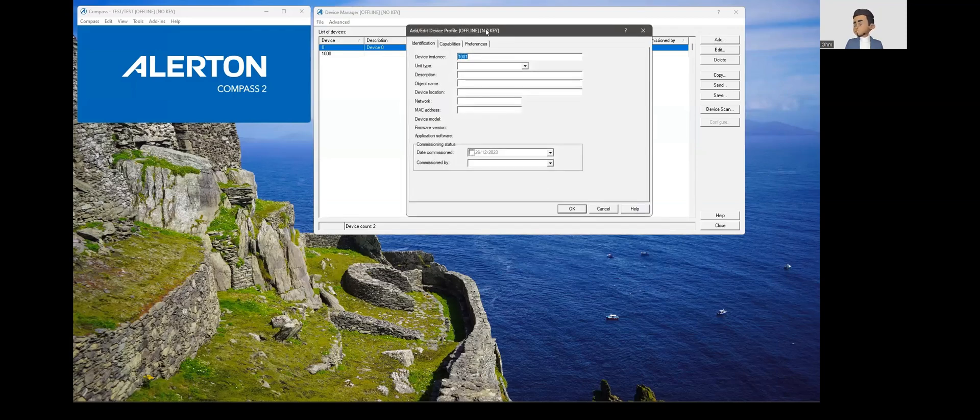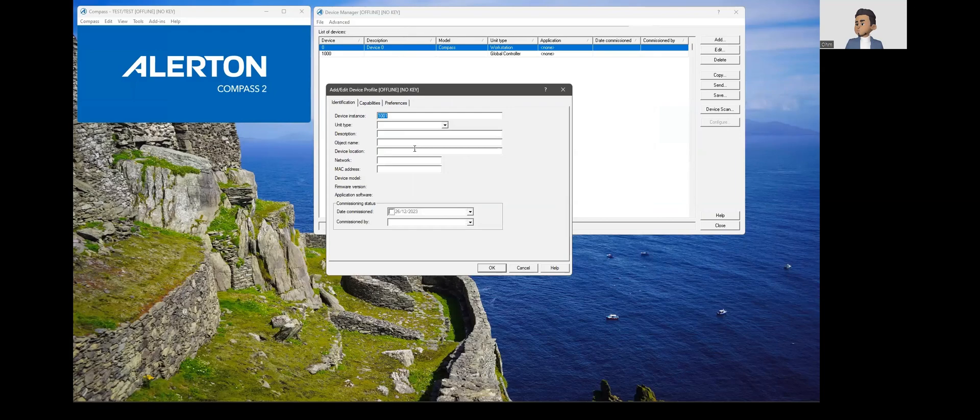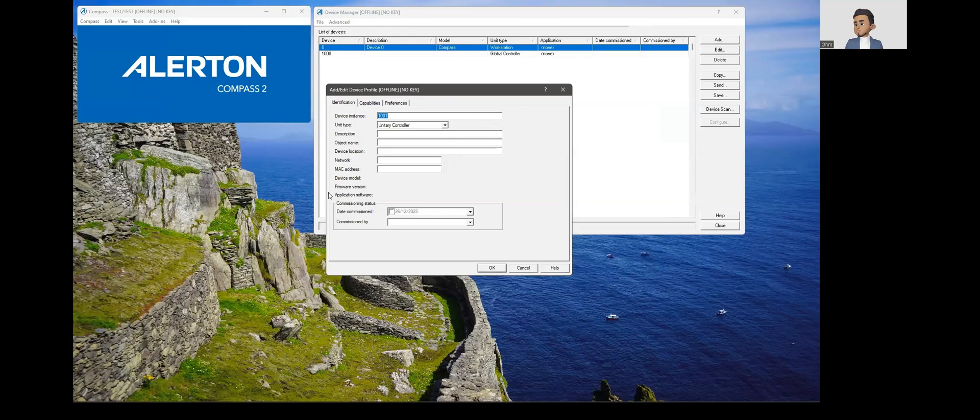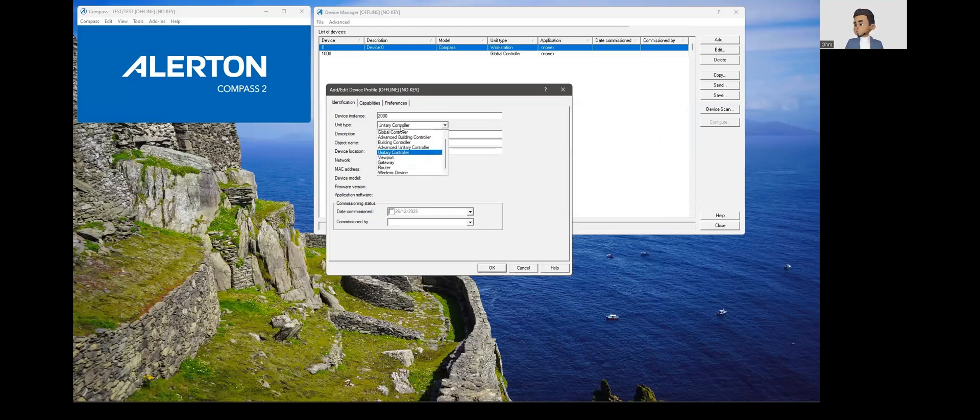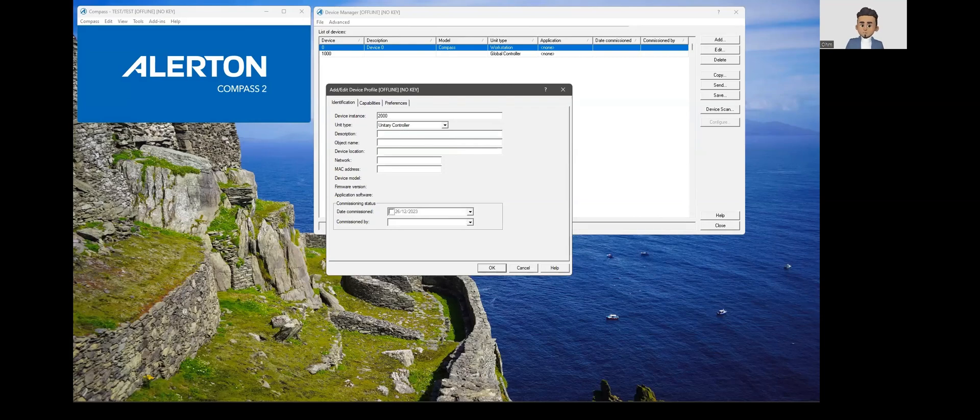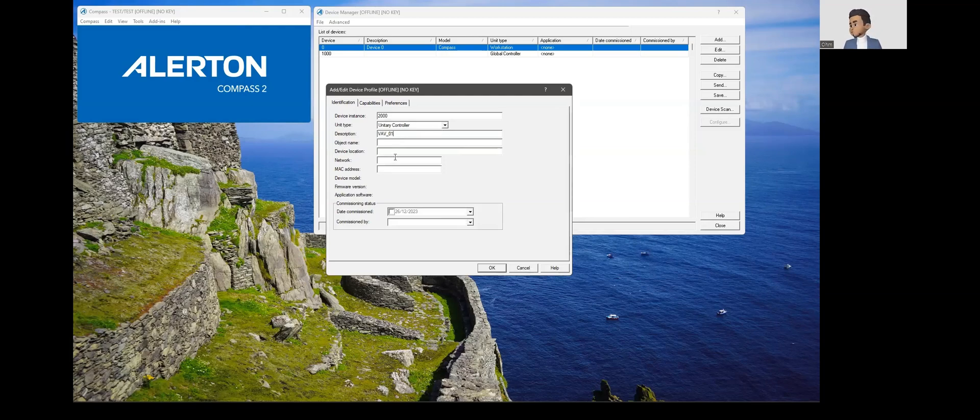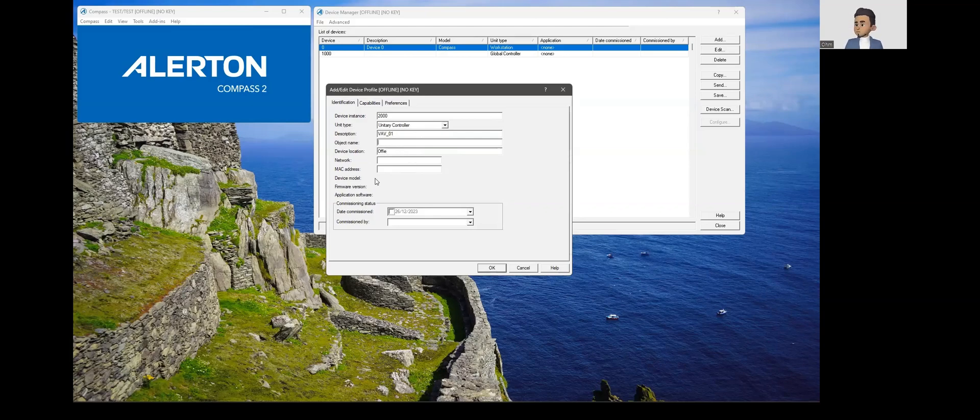Let's say there is a VAV controller. We will call that as unitary controller basically. Let's choose unitary controller and then we will call the device instance as 2000. Let's call this unitary controller a VAV. We'll call it as VAV01. Device location maybe office, then object name we could give the number 101.